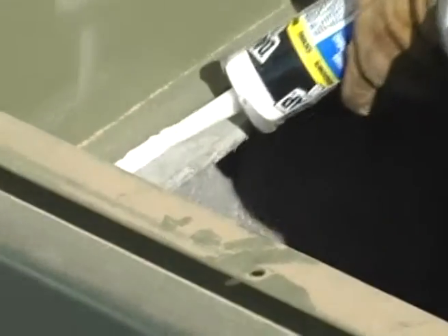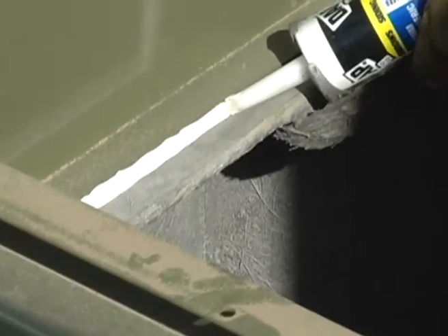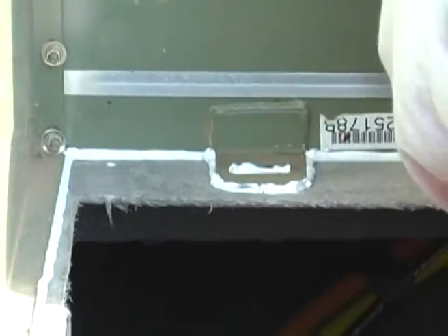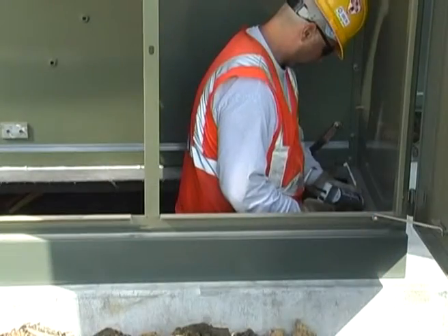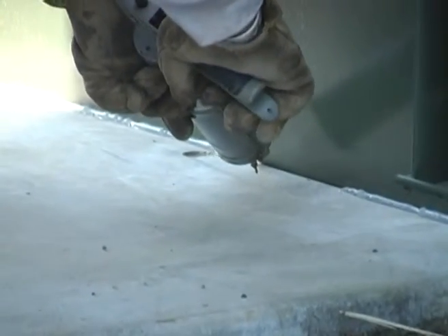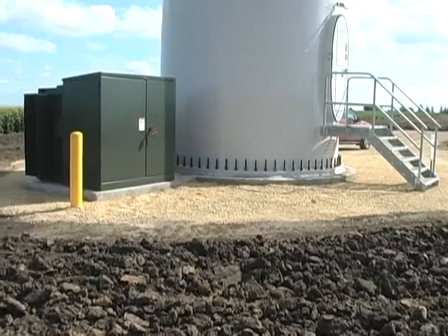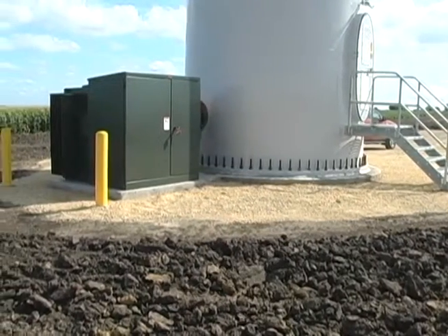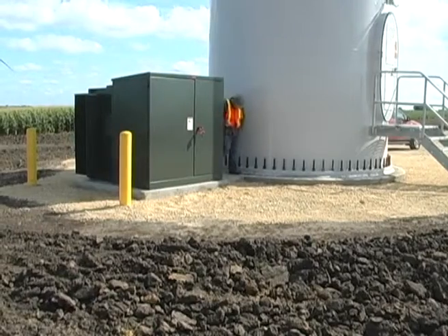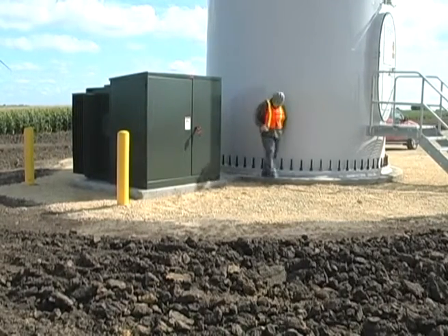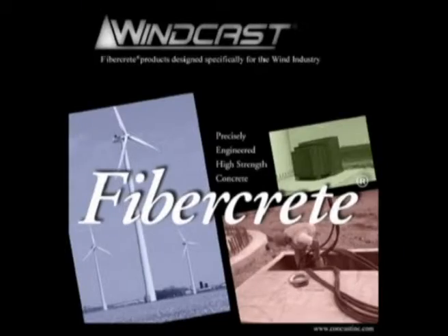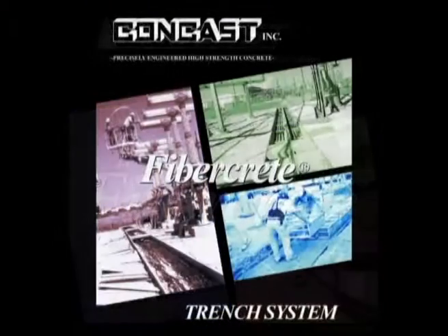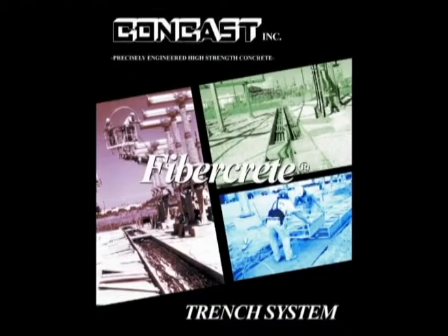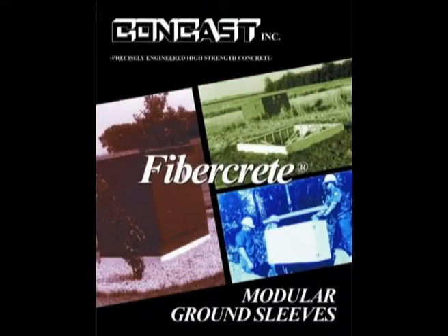All faces of the base that are in contact with the transformer are to be sealed, inside and outside. After the transformer installation is completed, a crushed stone is used around the generator pole and the transformer base to keep the weeds down.